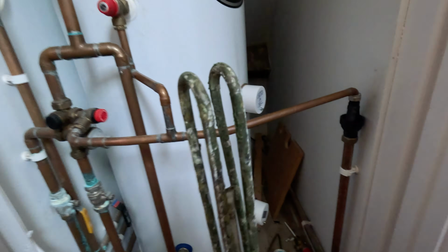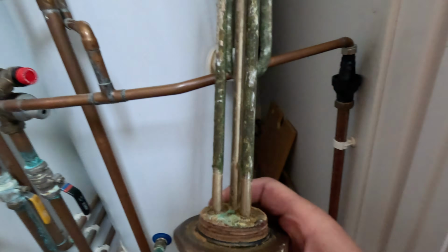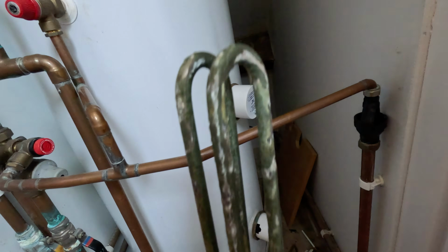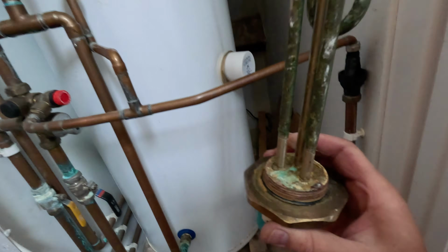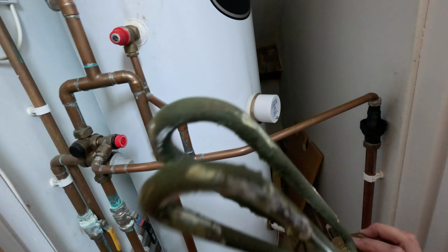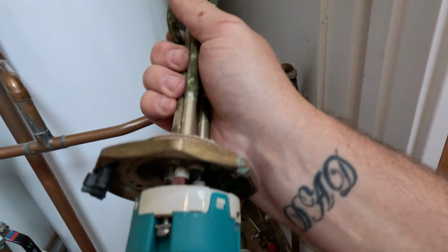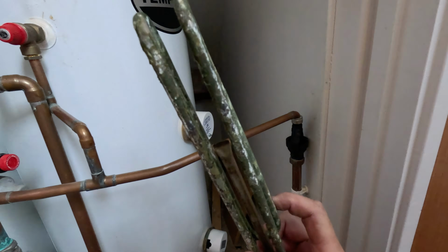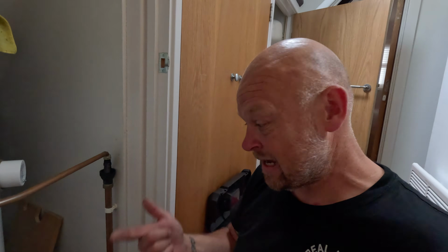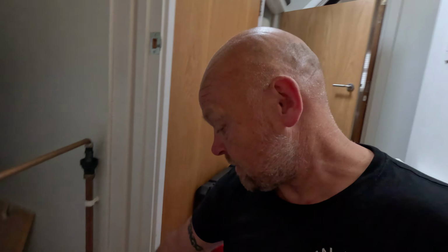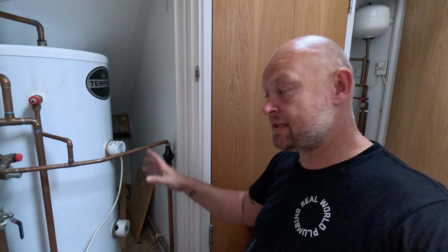And then I've also just been having a look over the old stat, and you can see how knackered the immersion heater element is, and all in there. So it's obviously been tripping out or just playing havoc with it. Even inside there, it's all manky and horrible. But where we are over in Warwick, it's hard water, so it eats through anything: kettles, taps, immersion heaters. Right, let's get it connected and get the power back on. There we go, all done, dusted, power cable connected back up, tested, it's warming up.